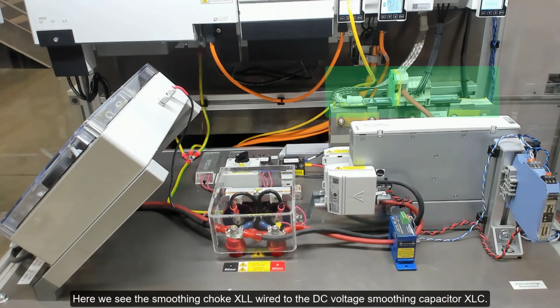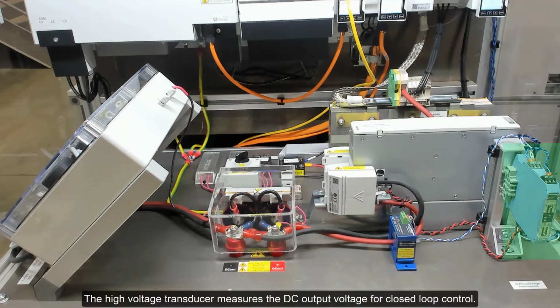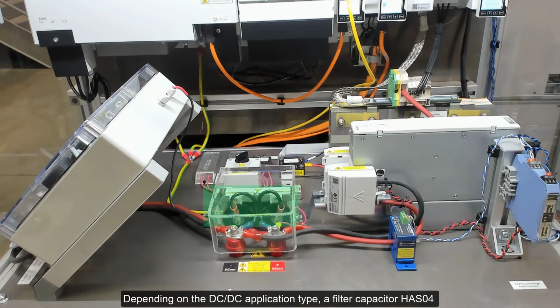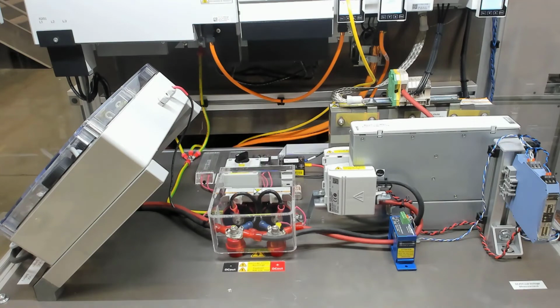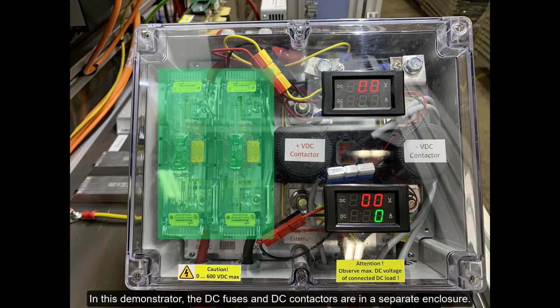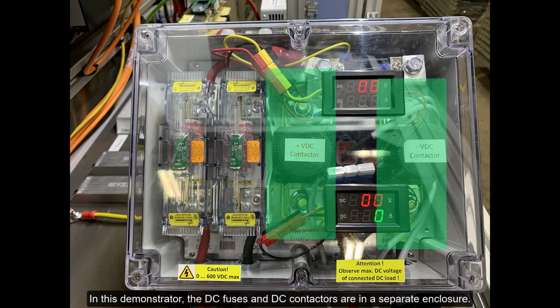Here we see the smoothing choke XLL wired to the DC voltage smoothing capacitor XLC. The high voltage transducer measures the DC output voltage for closed loop control. Depending on the DC-DC application type, a filter capacitor HAS04 and a discharge resistor for the DC smoothing capacitor is required. In this demonstrator, the DC fuses and DC contactors are in a separate enclosure.